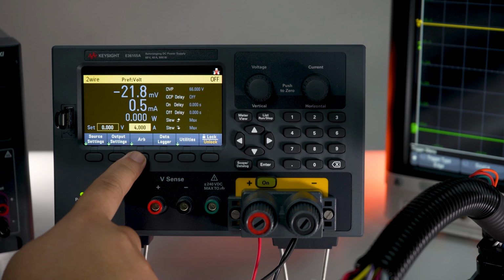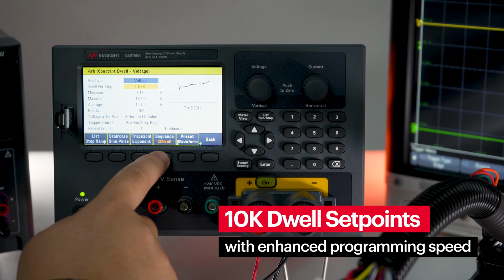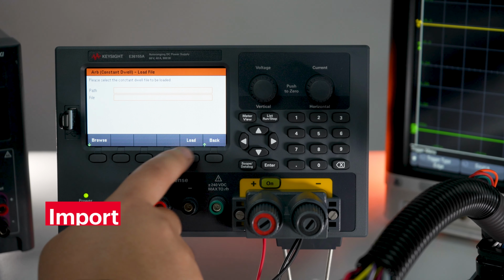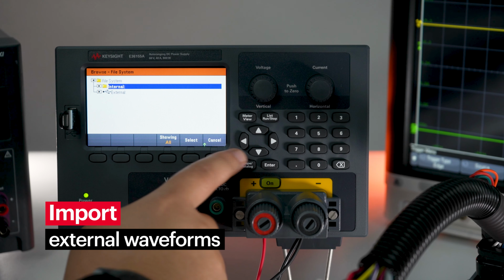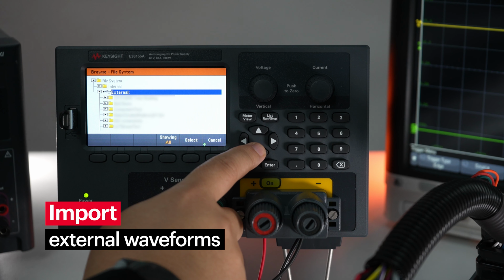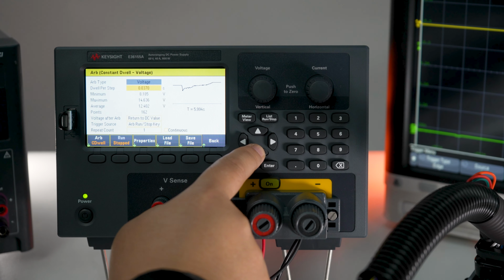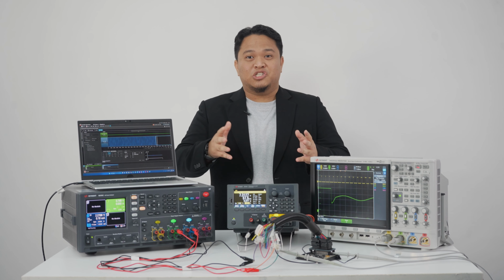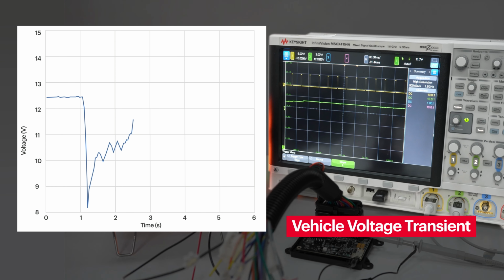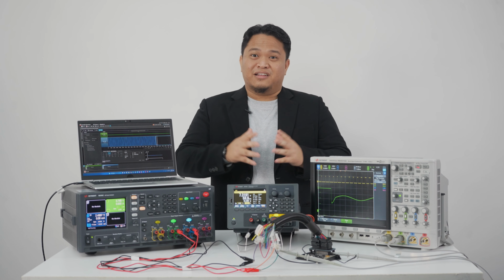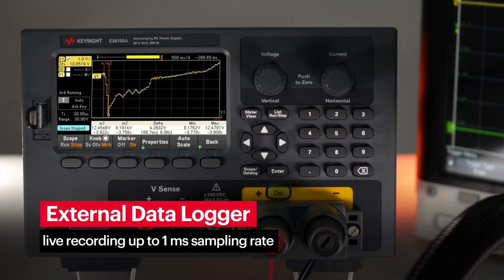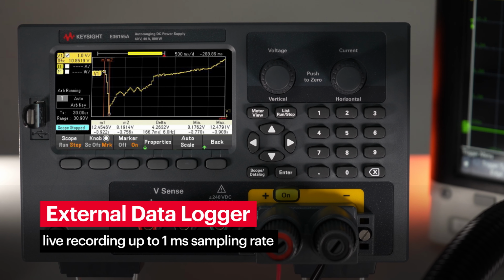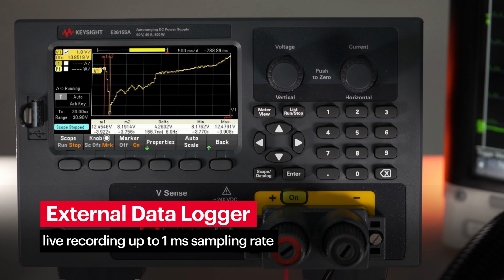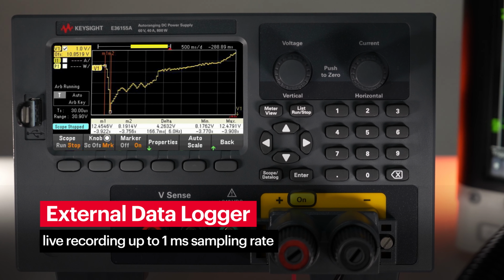Since the power supply now supports up to 10K constant dwell set points with enhanced programming speed, it enables you to import external waveform that contains fast transient response at higher fidelity and then run the playback simulation. This is particularly useful to test your ECU performance with the actual transient and disturbance condition in the vehicle captured with an oscilloscope. Not only that, the power supply also allows you to perform data logging up to 1 millisecond sampling rate with the SCPI command to capture the output waveform of your power supply with higher precision. Let me show you a quick feature demonstration.